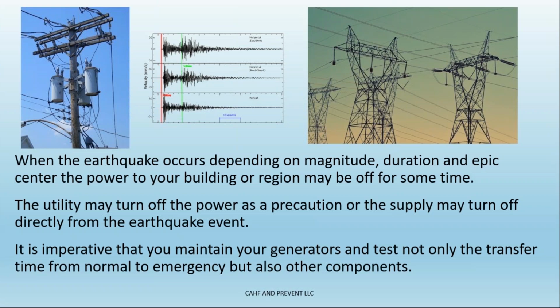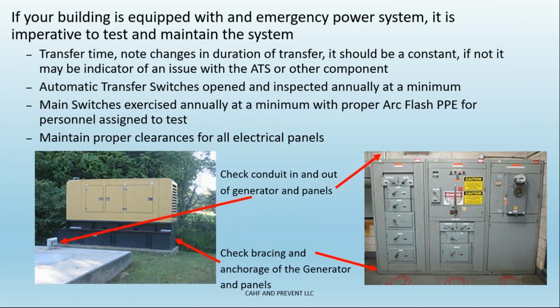It is imperative that you maintain your generators and test not only the transfer time from normal to emergency, but also all the other components connected to that system. Not every building or facility has emergency power. If your building is equipped with an EP system, or an emergency power system, it is imperative to test and maintain that equipment. You should have a backup to the backup, just in case your system fails while in use. Know who to call, have redundancy built into your program.